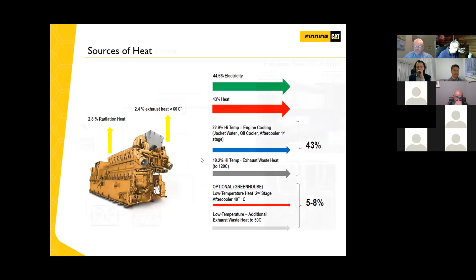If there's anything nasty in the fuel, such as H2S, SOx, that can also lead to acid production, cause damage with the genset and the heat recovery equipment attached to it. So clean fuel on this type of thing is a must. That extra 5 to 8% at the bottom, that's specific to greenhouses. And I will touch on that a little bit later. I would like to move on and look at hot water generation first.